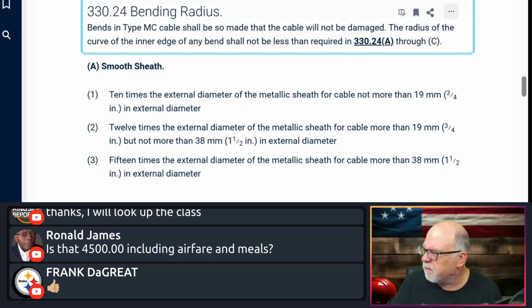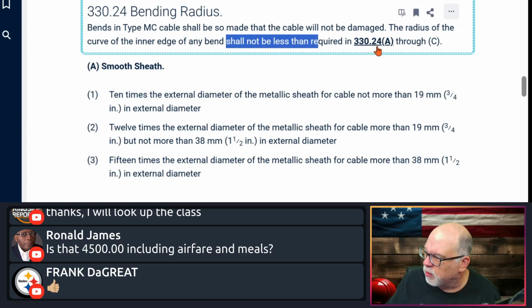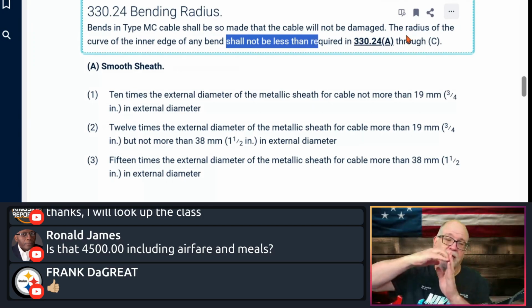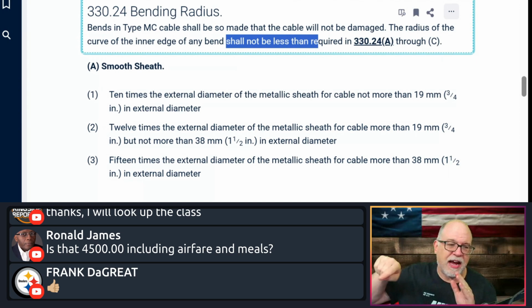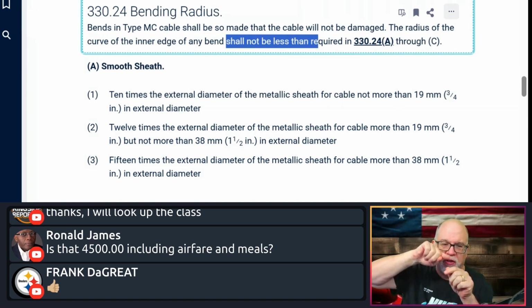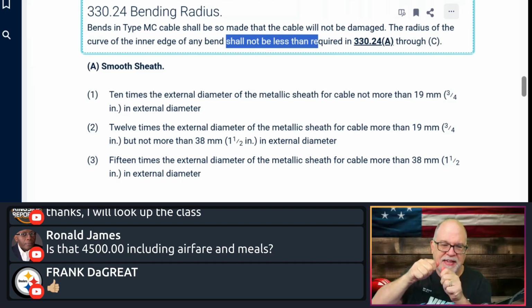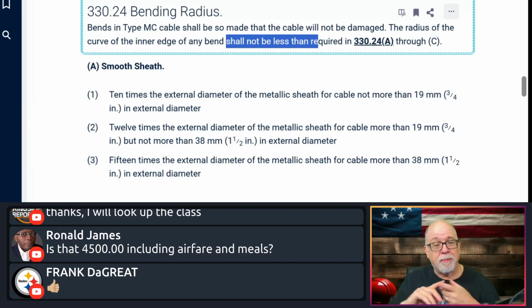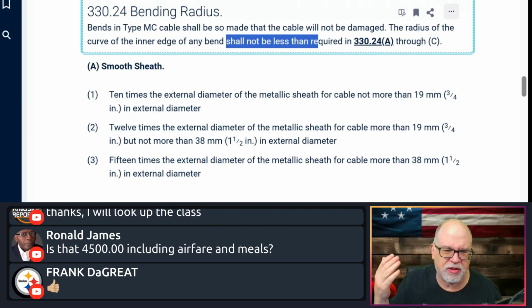Now, the radius of the curve of the inner edge of any bend shall not be less than the values required in 330.24(A) through (C). What that means is the inner bend has to be at least the values we're going to talk about here. From the point where the bend starts to the point where the bend ends, they can't be tighter than those values. And what are those based on? They're based on the OD of the cable, which every manufacturer publishes for their product.